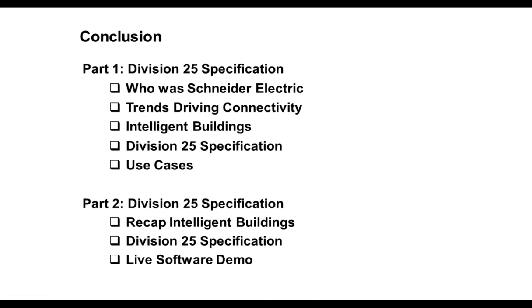23, if you didn't know, is the HVAC, but as a subset, there's controls. 26 is electrical, but there's also subsets of power and lighting control. When you look at 28, there's subsets of that being security, intrusion, card access, video, and then 25 is really a matter of tying the different systems together and getting that data to work together to provide a common functionality across the different divisions in lieu of standalone information. And we went through some of those use cases.